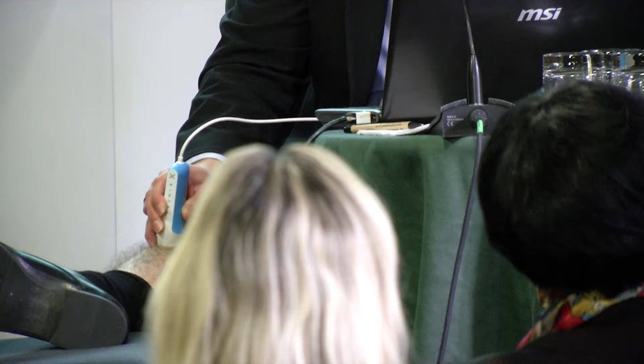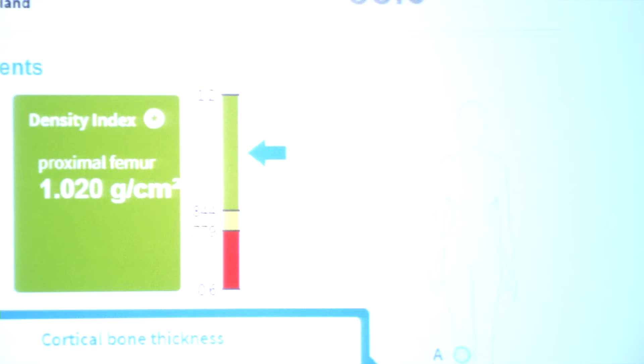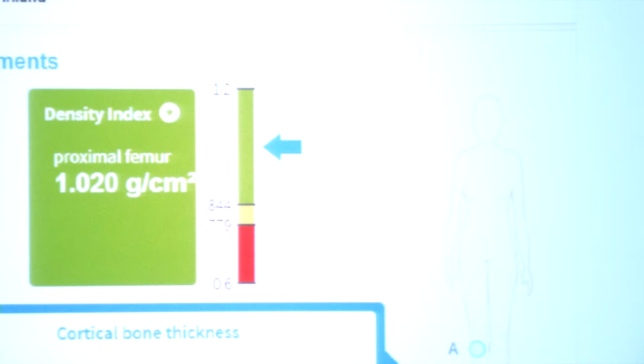The first echo comes from the upper surface, and the second from the inner surface. The time difference tells us the thickness. Here are all 5 measurements, and in this phase we also do a statistical analysis, comparing these measurements against each other. Now all are green, so this is accepted. Then we can continue and look at the results. Here we can see my cortical bone thickness was 3.2 millimeters. By the way, in my left tibia it is 2.8 millimeters, so there are differences between the sides.